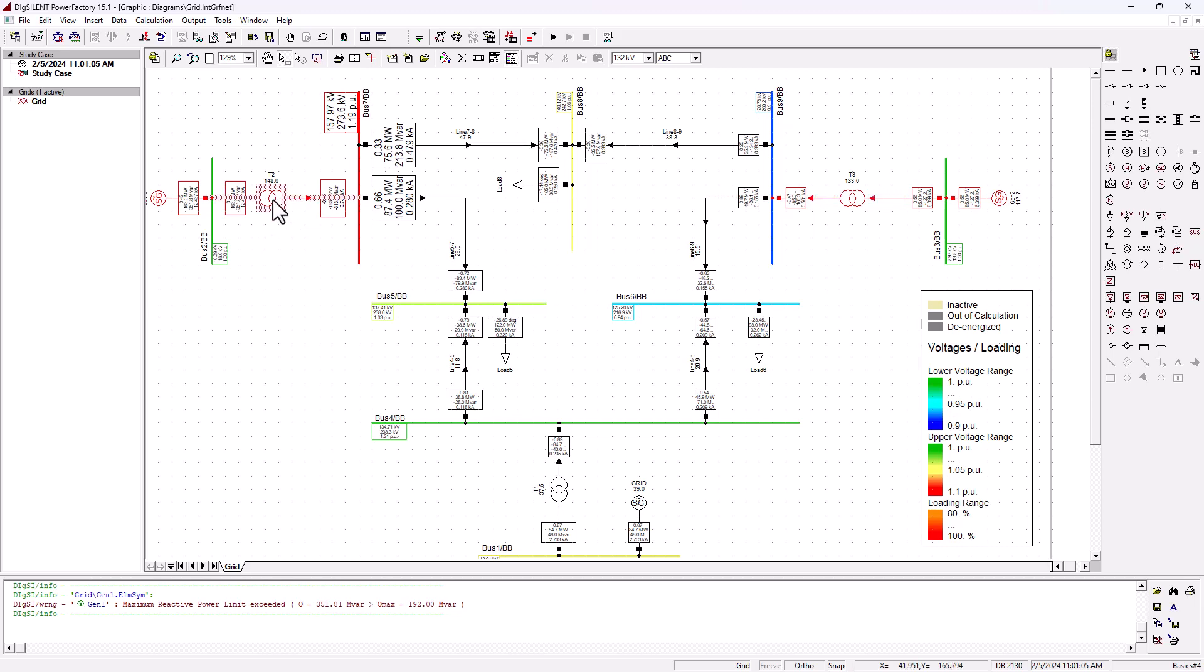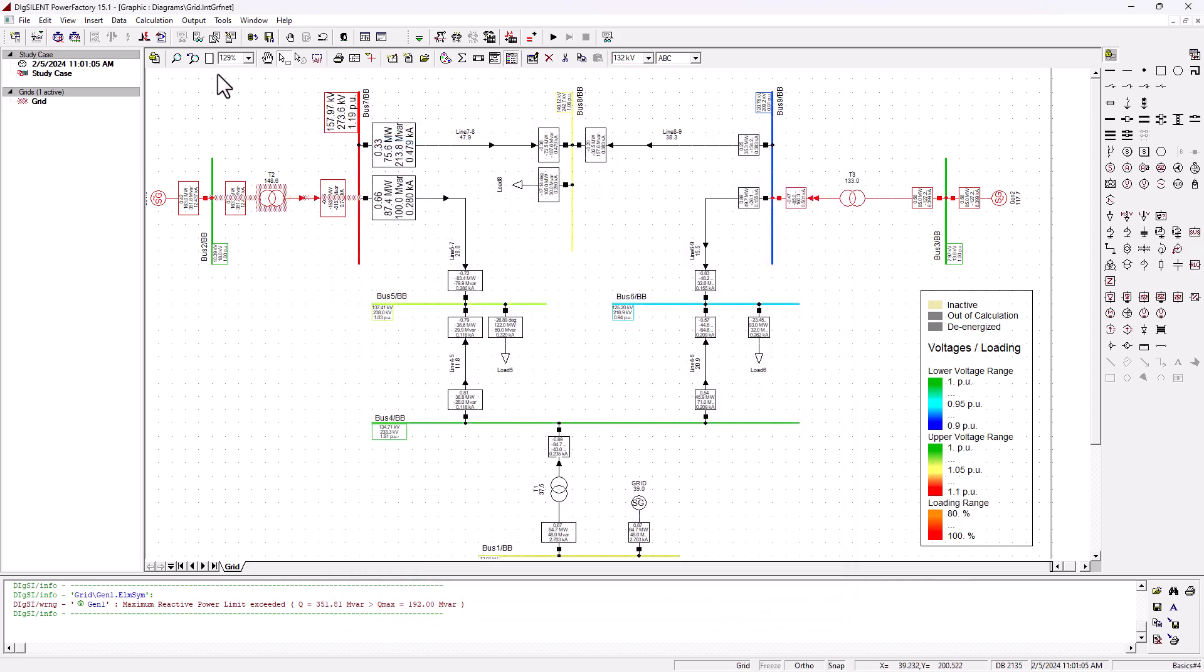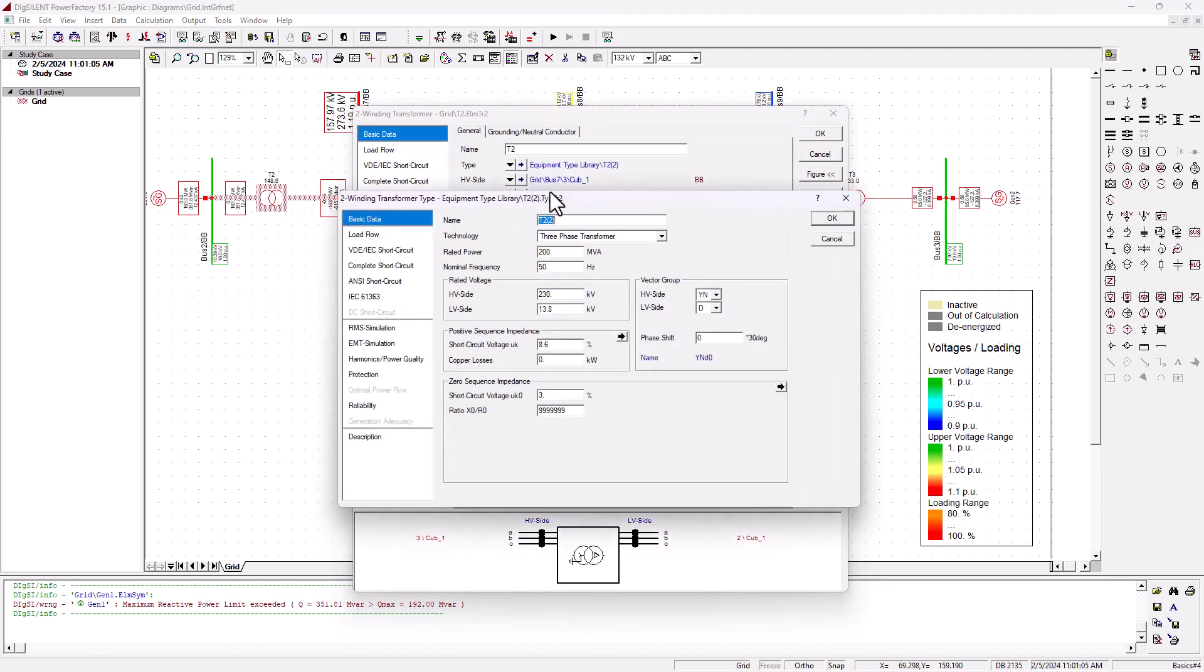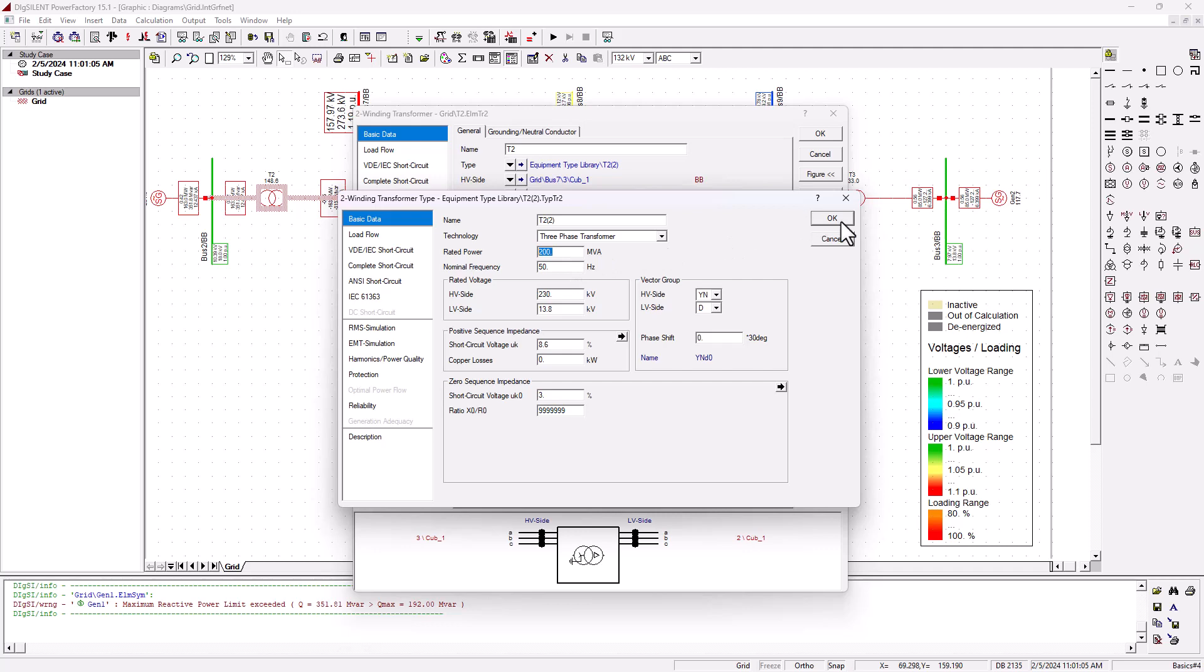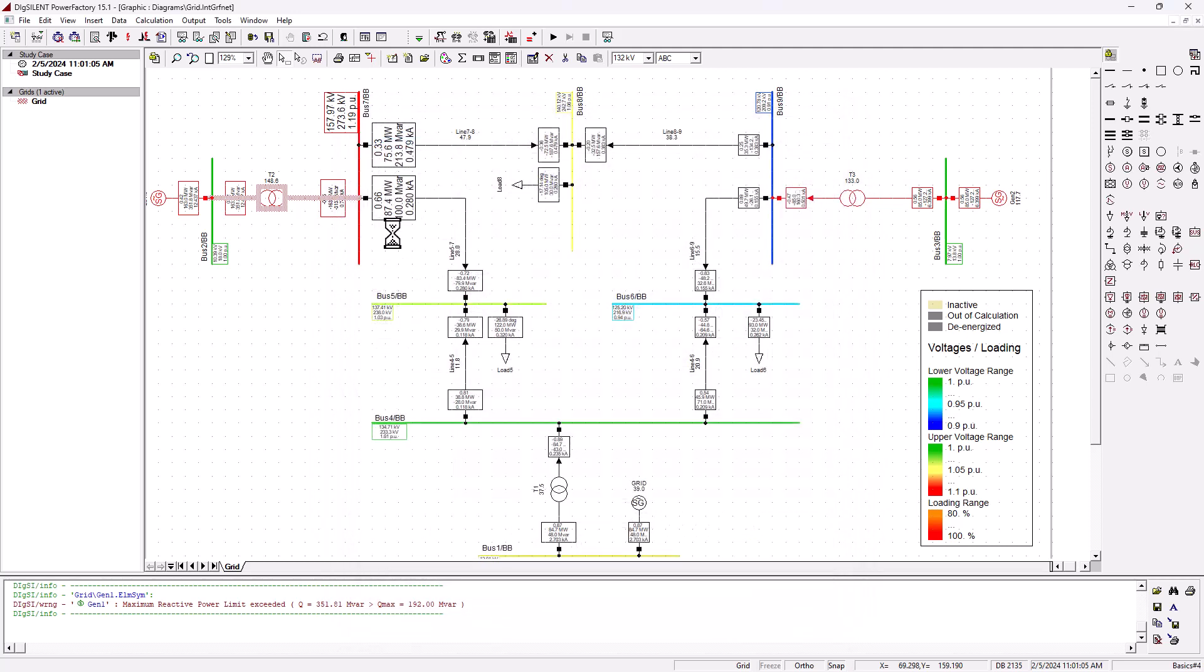That's a problem that we will have to attend to. If you come on this side, the same situation. We've got T2 that's also overloaded. Why is it overloaded? Obviously, you are drawing more than the transformer can supply. Let's first stop the load flow and double click.